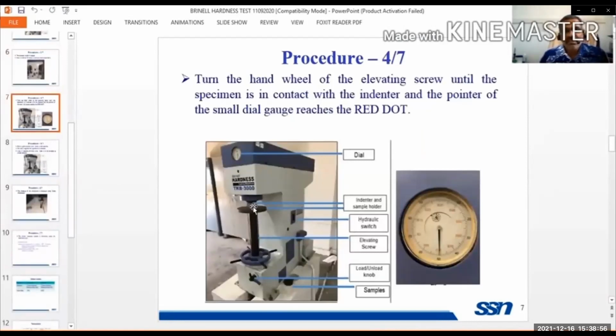This is the place where we have to fix the workpiece. By rotating the wheel, the screw moves upward, and the workpiece comes in contact with the indenter. Once the indenter makes the initial contact, there is a big dial, and inside it there is a small dial, and an indicator. When the initial setting is over, it can be confirmed by the indicator: the indicator has to reach the red spot and coincide with it.